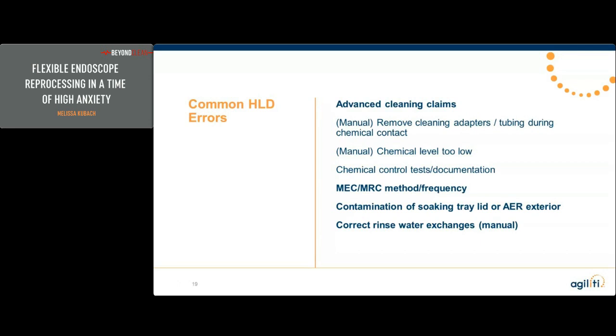This is also not supported by the FDA or CDC, and even one of the manufacturers that made the claims discourages someone from using them. So I always say really, really understand that and double check your cleaning policy. I often find when I'm auditing that the policy says every step will be performed per the manufacturer's IFU.